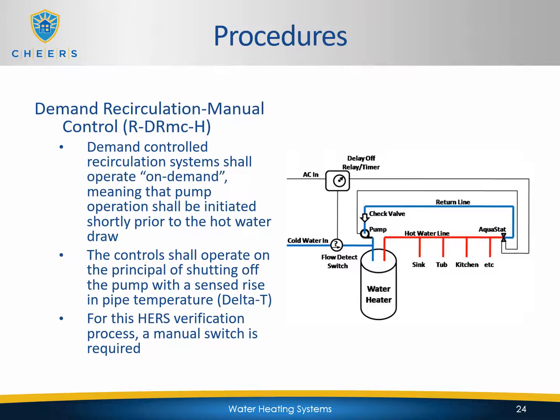So when a homeowner wants to utilize a fixture at a sink, for example, and they want to use the hot water, instead of turning on the hot water valve and letting it run and run until all the cold water's been replaced or evacuated from the line and it's now bringing in hot water, they'll press a button or flip a switch, and that'll turn on the pump. The pump will then run and pump hot water through that line, so that when they do turn on the fixture, it's a very short period of time before hot water starts coming out, so it helps stay with water savings. And then you have this thermal switch that will sense that the hot water has made its way all the way through the recirculating loop, and the pump is no longer needed, so it will then automatically turn that pump off.